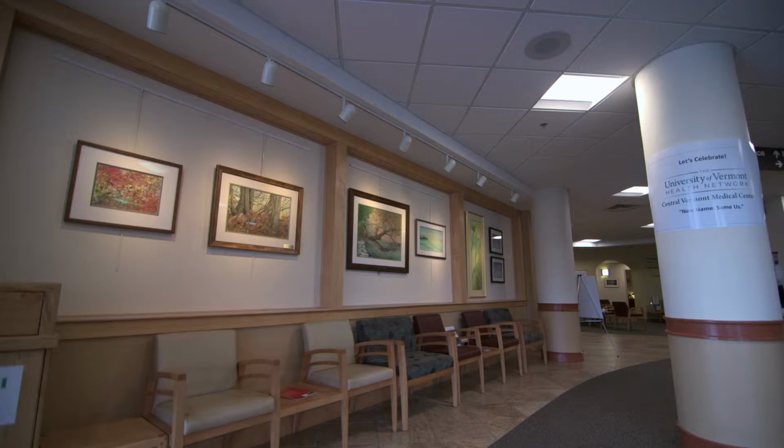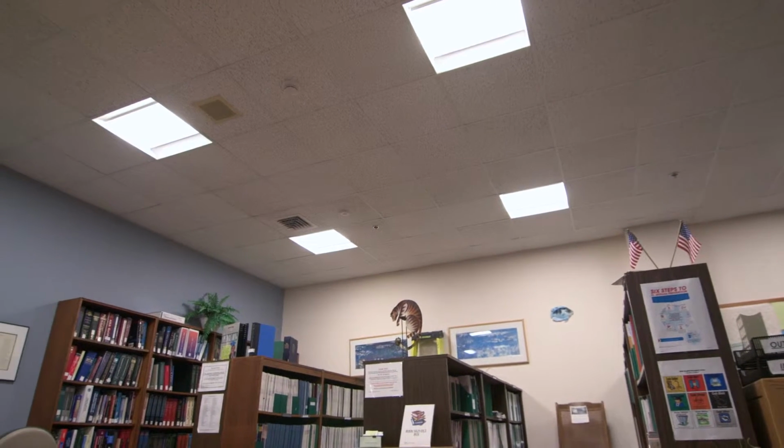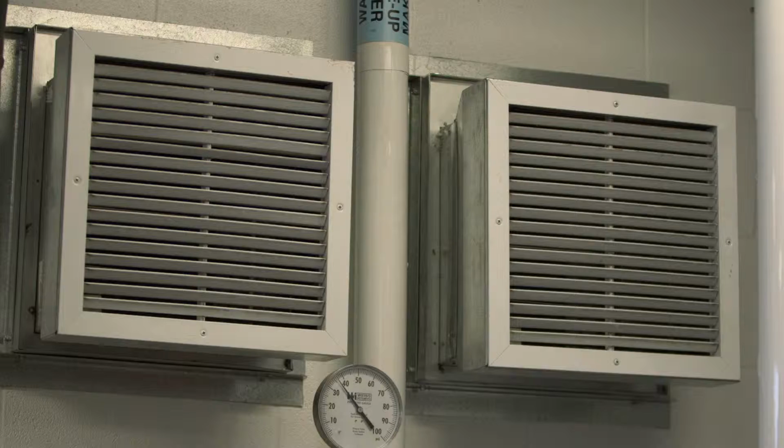One of the things that we discovered is that the whole hospital was running occupied 24/7. We created unoccupied programs for all the different boxes throughout all these departments. Once we instituted one air handler having this unoccupied mode, your electric bill for that air handling went down $600 a week.